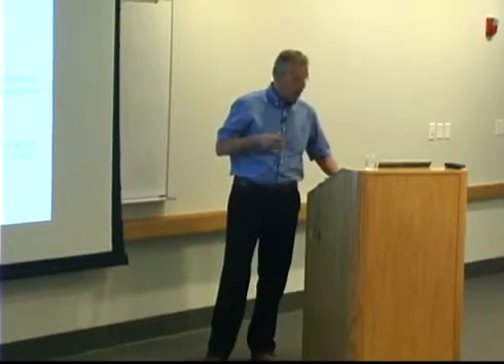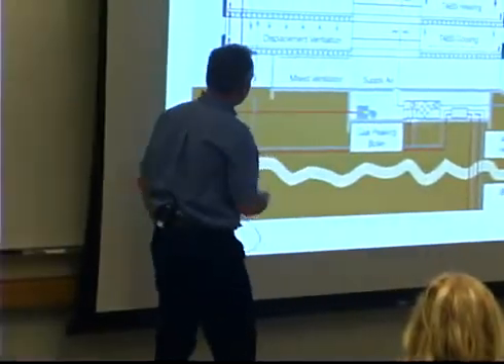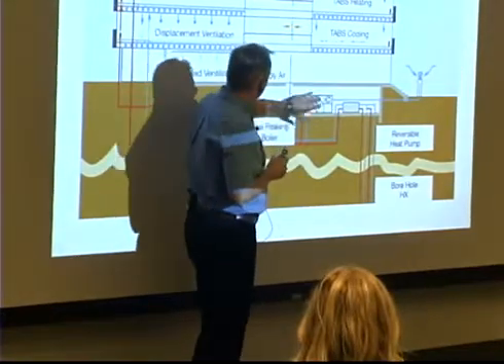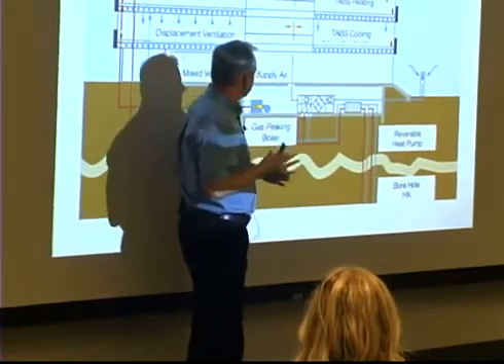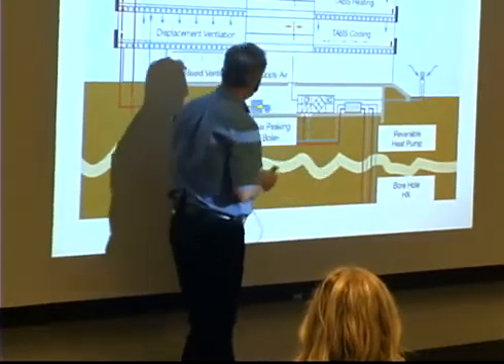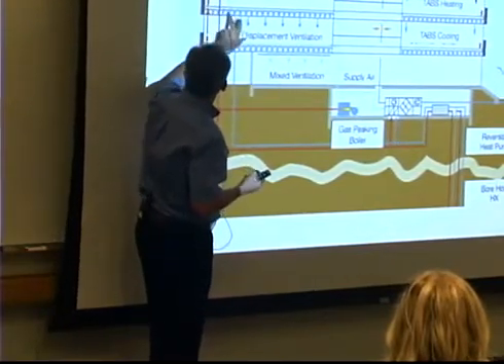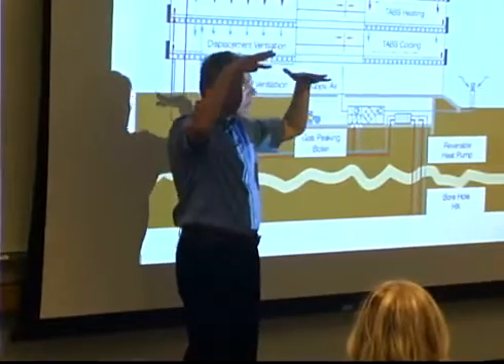What we've learned is that high performance buildings tend to come with a few design features. The state of the art, and that's my opinion, typically involves some form of ground source heat exchange system. It has a heat pump here that provides heating and cooling. It has a dedicated outdoor air system, which separates the sensible and latent ventilation loads from the building loads. So we can focus on the ventilation separately with these systems. The building involves fairly massive construction with radiant heating and cooling systems. In this floor, we have radiant cooling coming from the thermally activated building structure. So again, you have a layer of concrete above you that radiates, cools down.